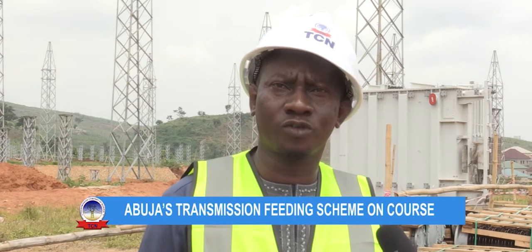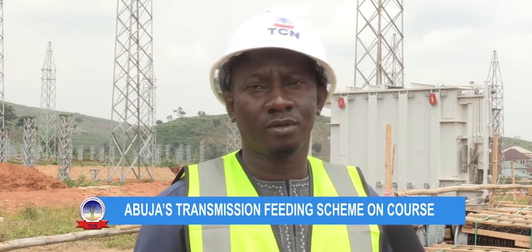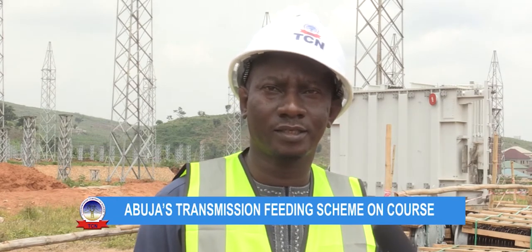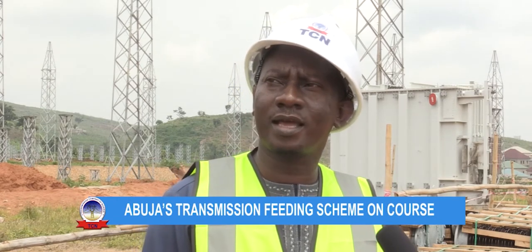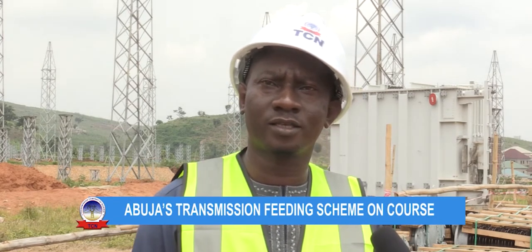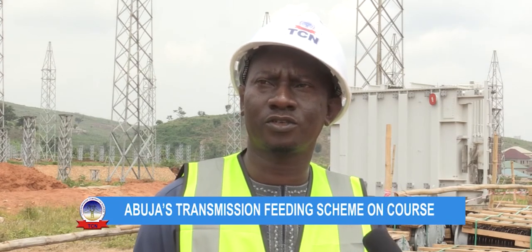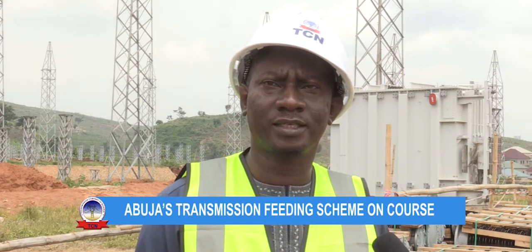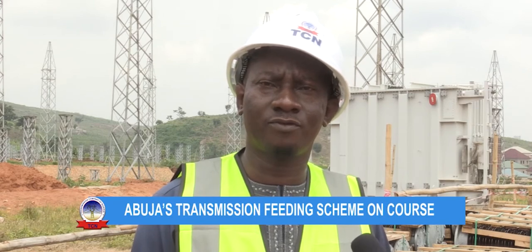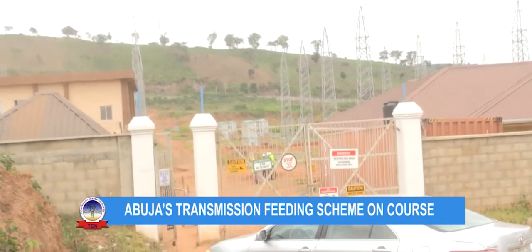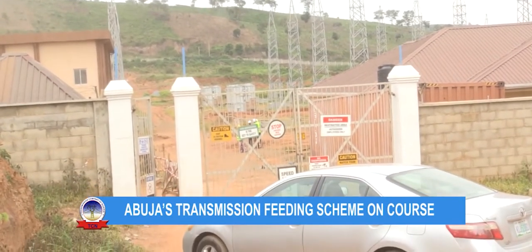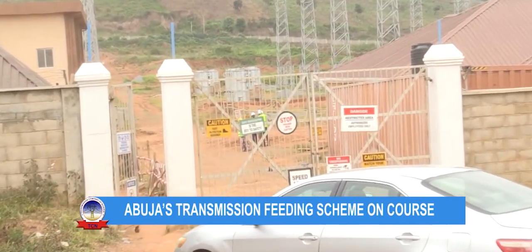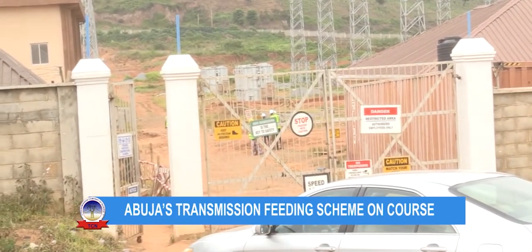At this location, we are supposed to have about 240 megawatts from the upstream, and at the downstream - that's the 132 section of the station - we are having 3 by 60 MVA, that's 180 MVA, tantamount to 144 megawatts that will be consumed by the district and the Abuja environment.